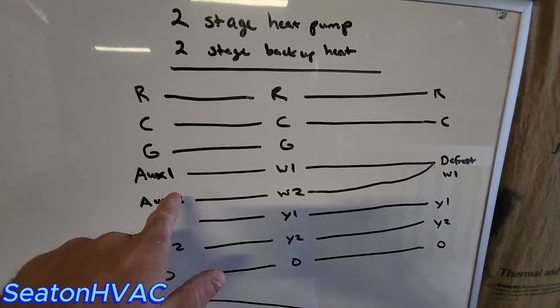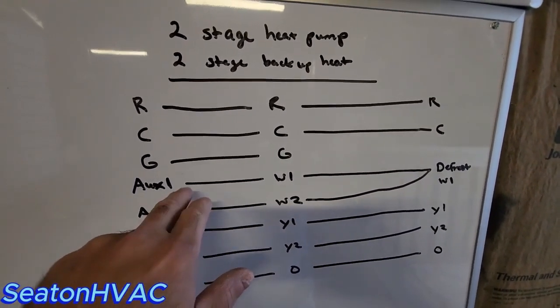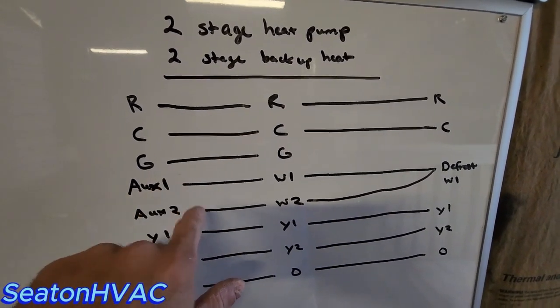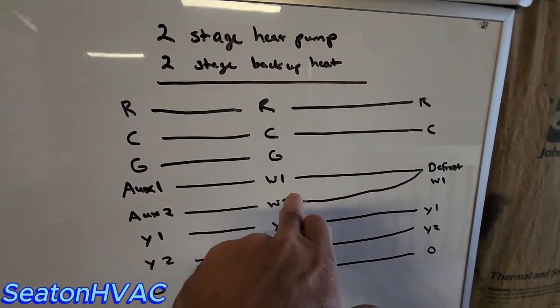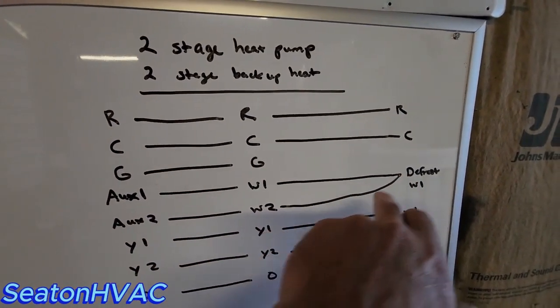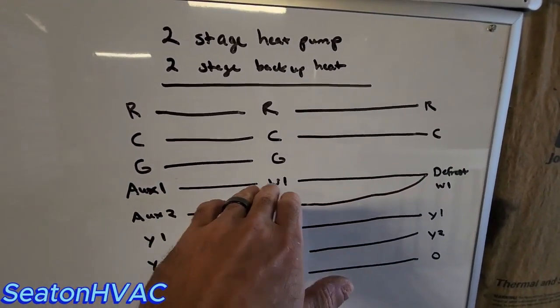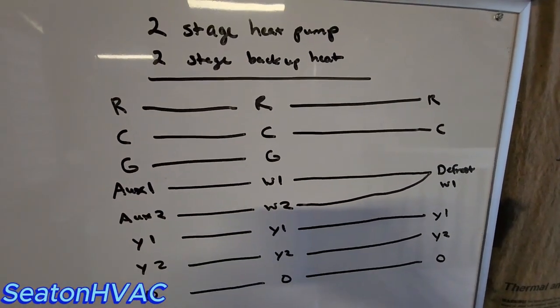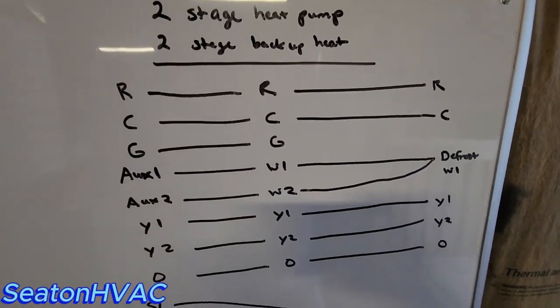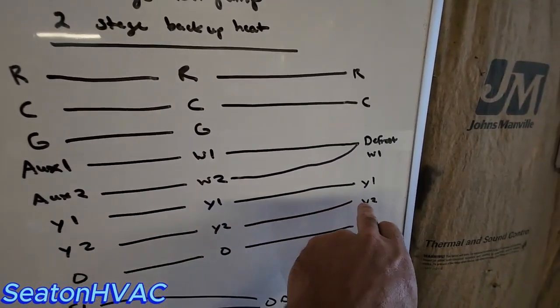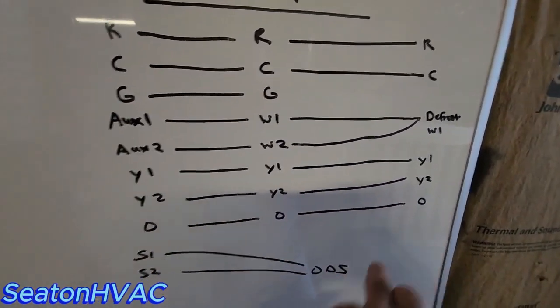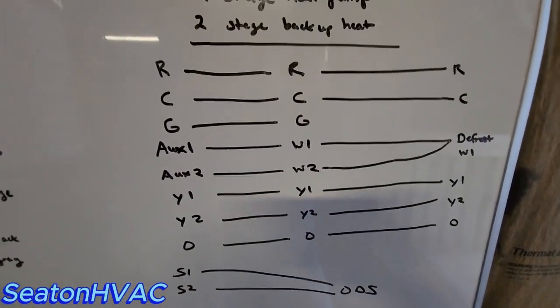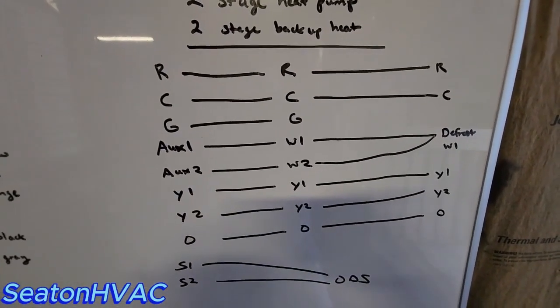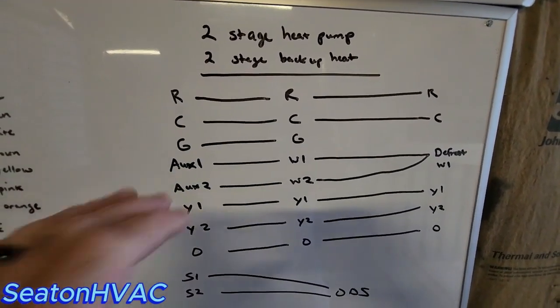I recommend it anyway. And another way you can do it too is you can have these staged on an outdoor sensor as well. It just gets a little complicated that way. Usually a smart thermostat can do it timed. So, if it doesn't reach temp within a certain amount of time on your backup, it'll kick in that second stage. So there's programming in the thermostats that'll help you with that. First stage compressor outside, second stage of your compressor outside, and then your reversing valve again, and then your outdoor sensors. So I don't want to get too crazy with going over this too much, as opposed to what I showed you already, because it's the same. But this stuff here is a little bit different.